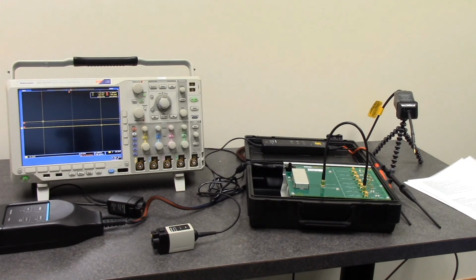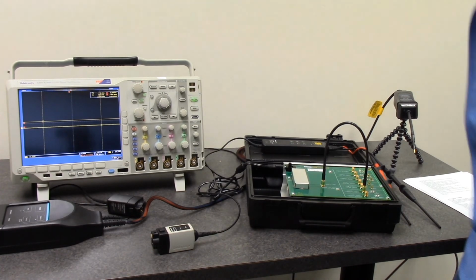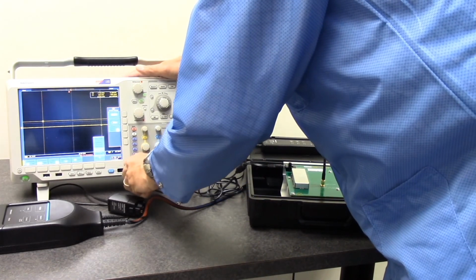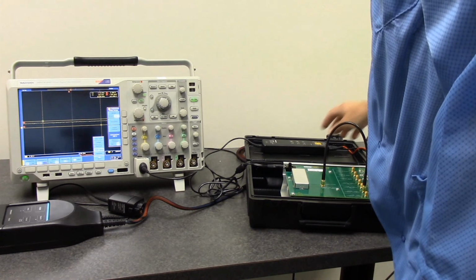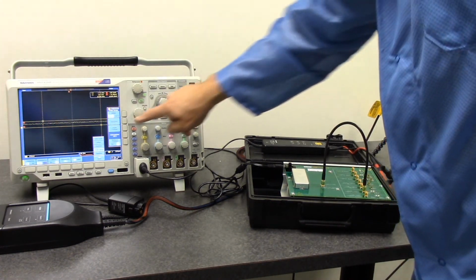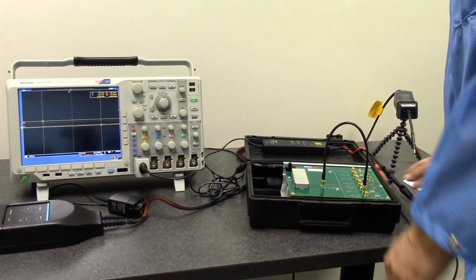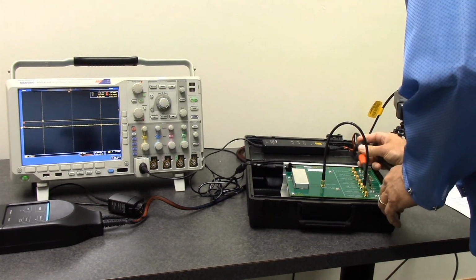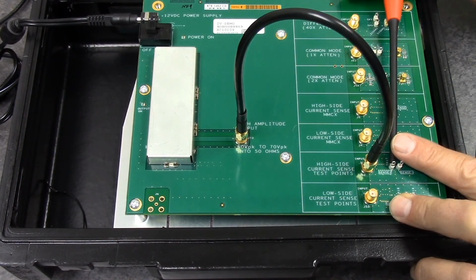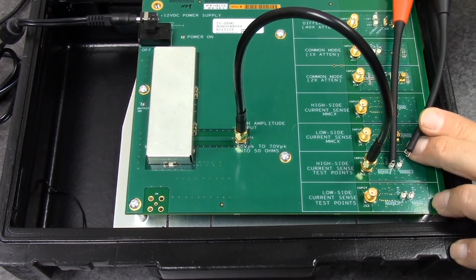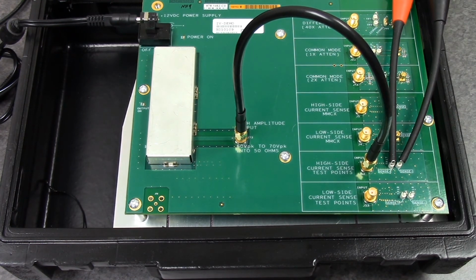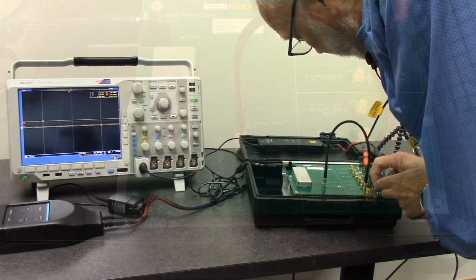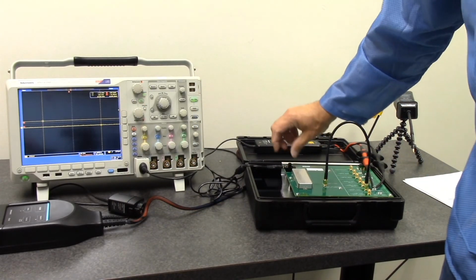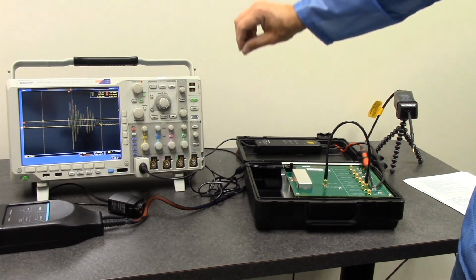Now we're going to do the same measurement on a high side current sense resistor using the TMDP0200 probe. We'll plug it into channel 1, set it to 75 volts, do an auto zero. Then we'll connect the probe tips to the test point, with the positive or red probe going to the sense plus test point and the black probe to the sense minus. Then we can turn the demo board back on.